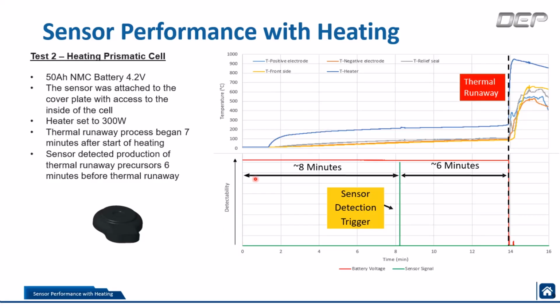So you can see here that because this was heating, voltage of the battery did not change. But within 8 minutes, we are still able to detect that there were electrochemical changes happening inside the cell. 6 minutes after that, the cell went into thermal runaway. Now, in this case, there was no voltage, but the temperature did fluctuate in this range where the detection happened, somewhere between 60 to 80 degrees Celsius.